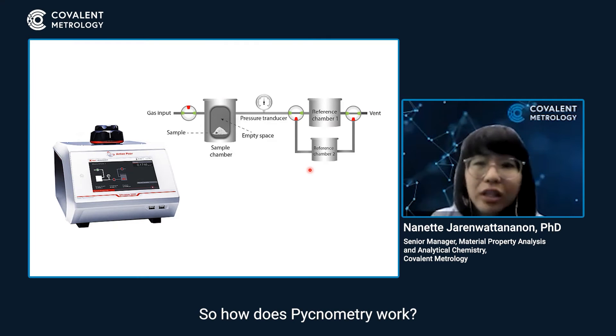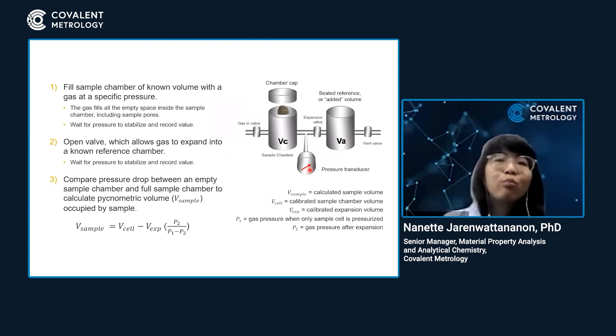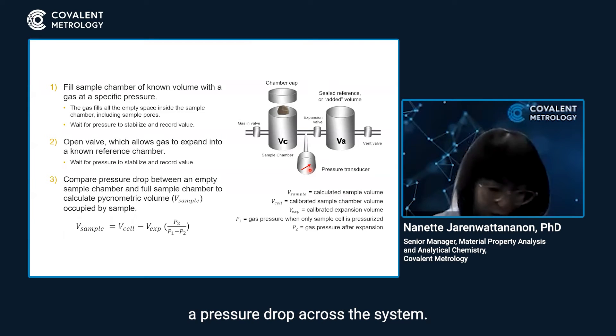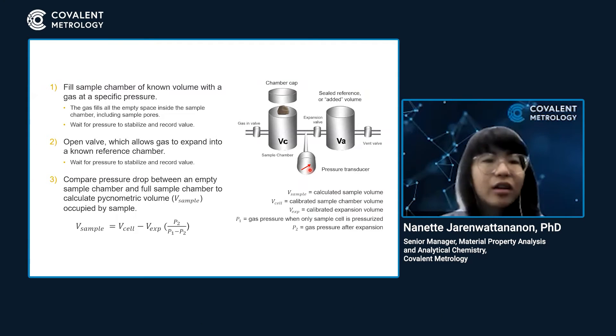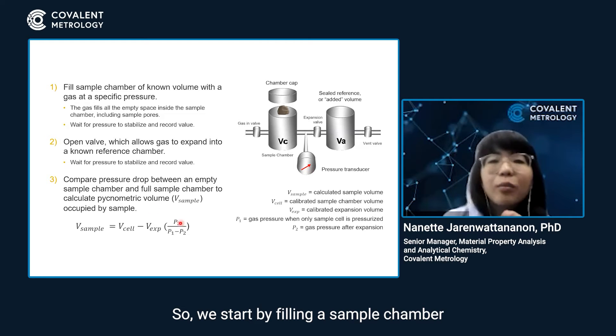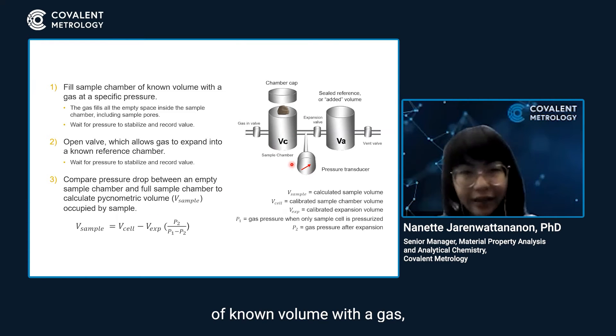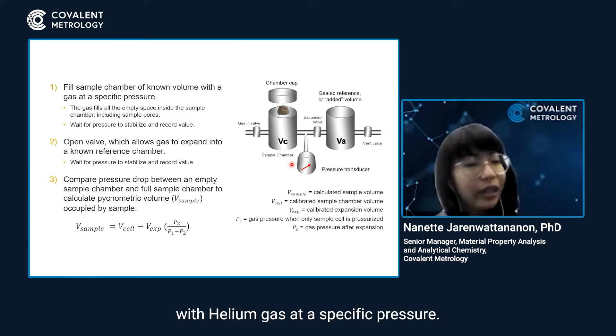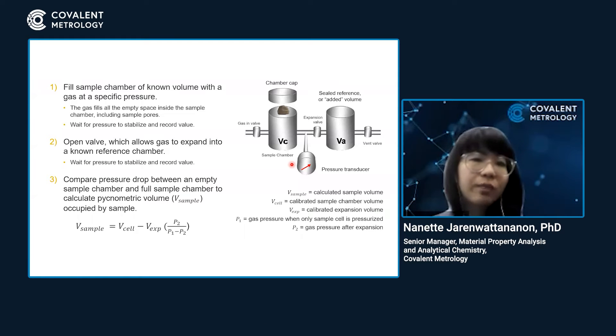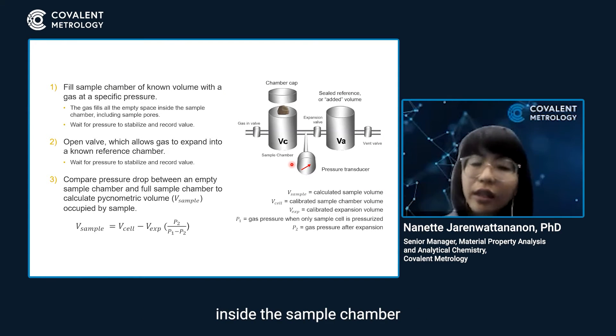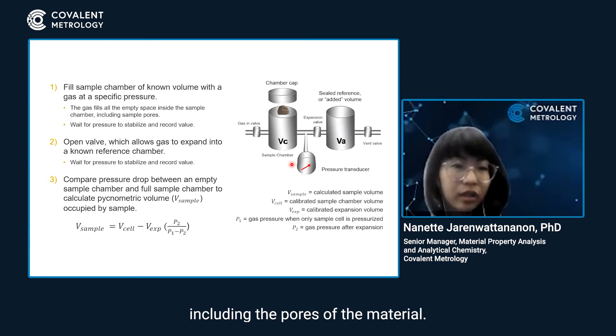How does pycnometry work? Pycnometry works by measuring a pressure drop across the system. We start by filling a sample chamber of known volume with helium gas at a specific pressure. The helium is going to fill all the empty space inside the sample chamber, including the pores of the material.